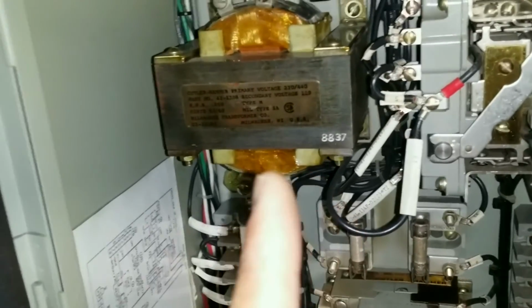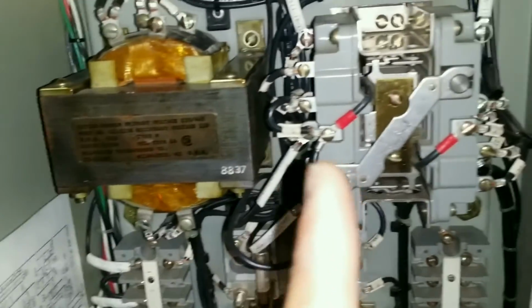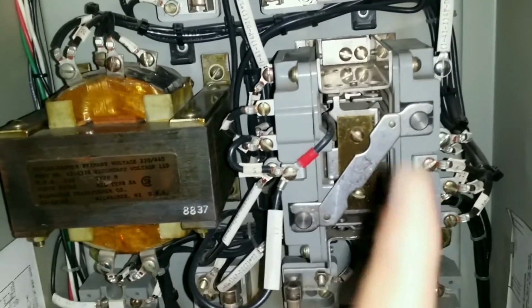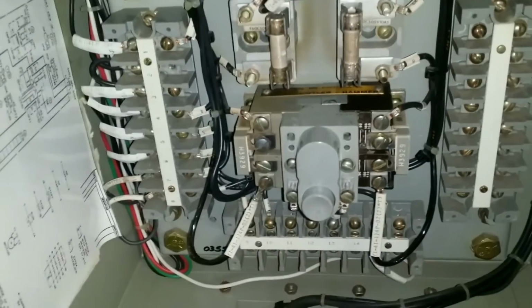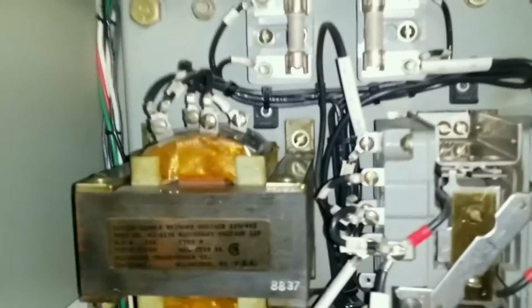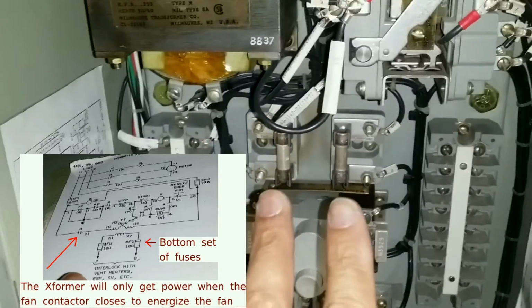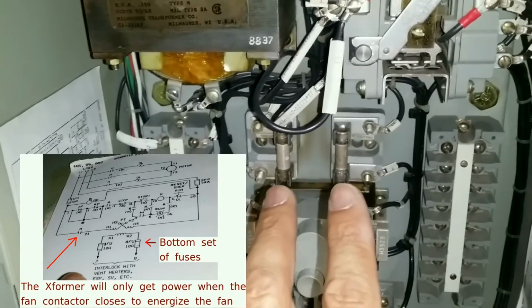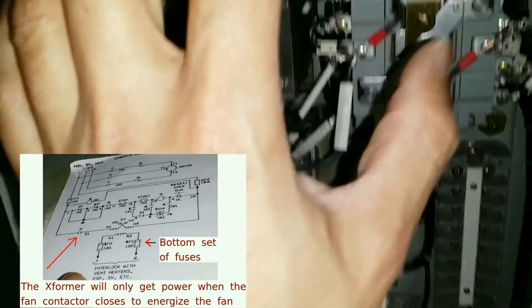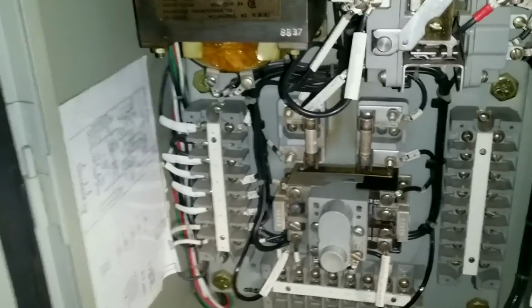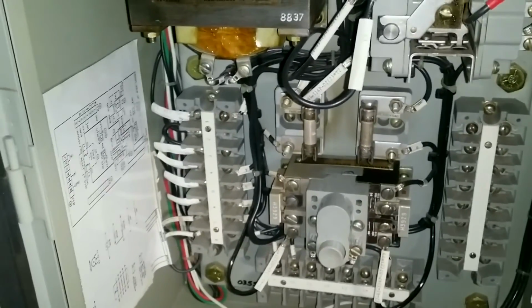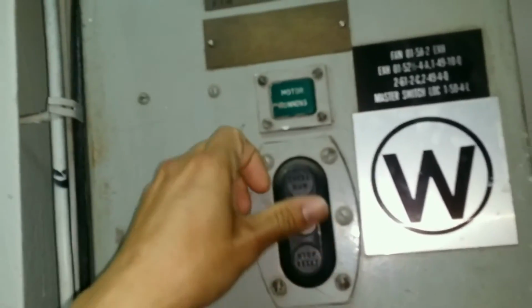Ventilation controllers typically have one step down transformer to 110. For single speed motors, you will have only one contactor and then the overload protection for that particular motor. There are two sets of fuses. Now that will be for control power on the heaters. If we lose power to this whole ventilation controller, the heater controllers will lose power, but they will still be energized by 440. Some ventilation controllers have their own start and stop buttons.